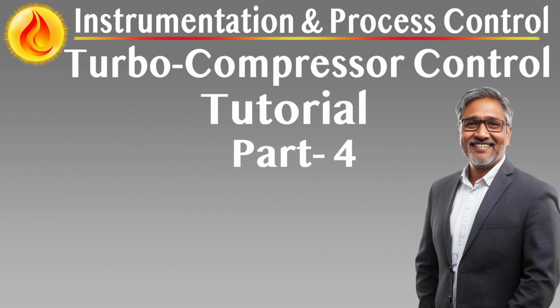Programming, configuration, and software. Structured engineering framework for safe, modular, and maintainable control logic. Software philosophy and standards. The Turbo Compressor Control System TCCS is engineered using a structured, standards-based software development approach that emphasizes reliability, clarity, and long-term maintainability. All programming and configuration activities follow IEC 61131 standards with an emphasis on modular design, documentation, and change traceability. The goal is to ensure that every software component, from control logic to HMI configuration, is robust, verifiable, and easy to update during future expansions or troubleshooting events.